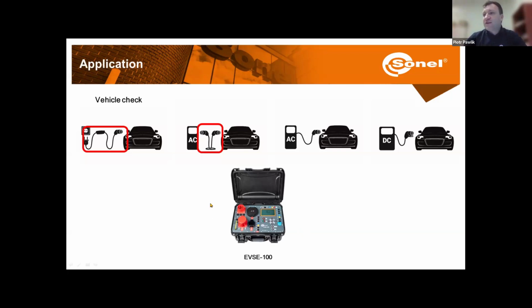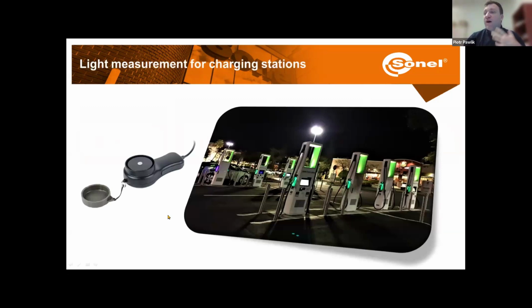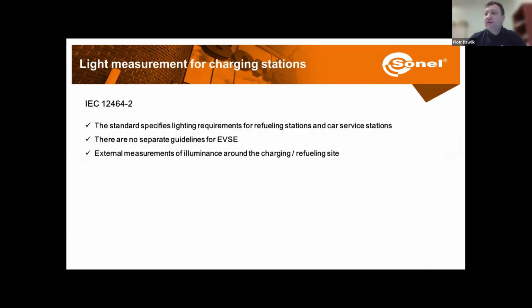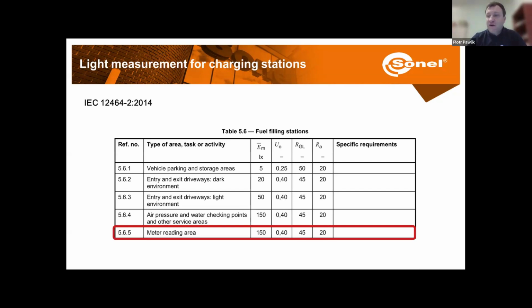Okay, so those were the safety electrical checks. One more thing that we need to check is the light intensity measurement. And here we have the standard IEC 12464, which requires checking light on the refueling stations. It does not specify what type of fuel it is. Is it gasoline? Is it electricity? Is it something else? It just says that the meter reading area should have 150 lux. So that should be the light intensity in the meter reading area.